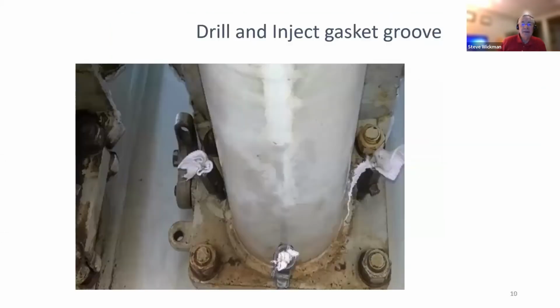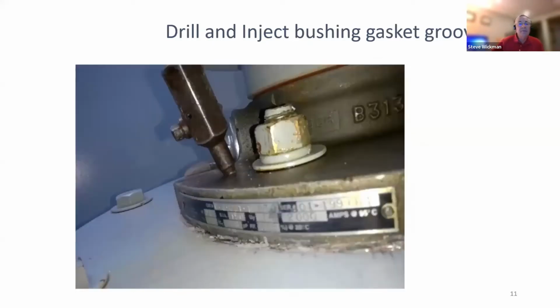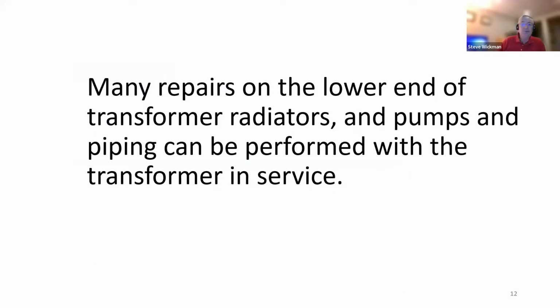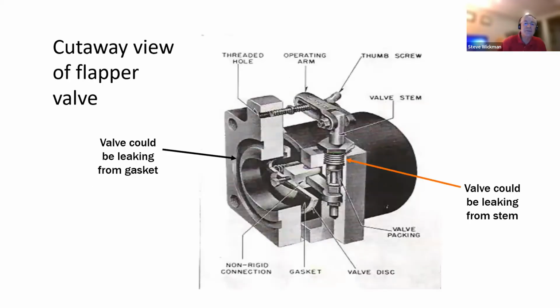Another picture of multiple injector valves in place going around the gasket groove on another style of radiator flange here. Just little pieces of rag tucked in there to contain the drips and keep the work site a little bit neater and cleaner in this situation here. And on occasion, we can drill and inject into a gasket groove on a bushing. Not only just flanges, but even on bushings if it's the right type of configuration. Just to highlight, many of the repairs, particularly on the lower end of transformer radiators and pumps and piping, can be performed with the transformer in service.